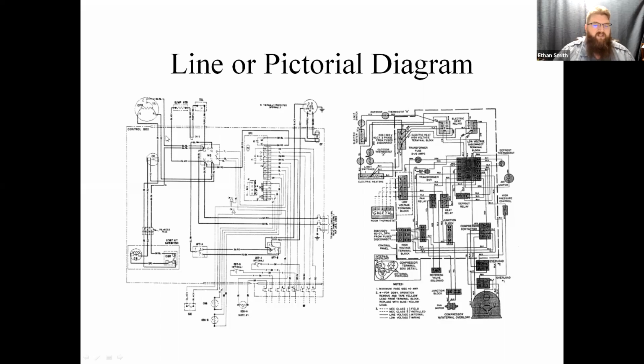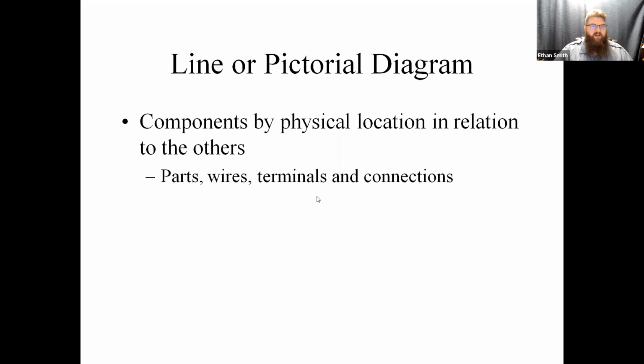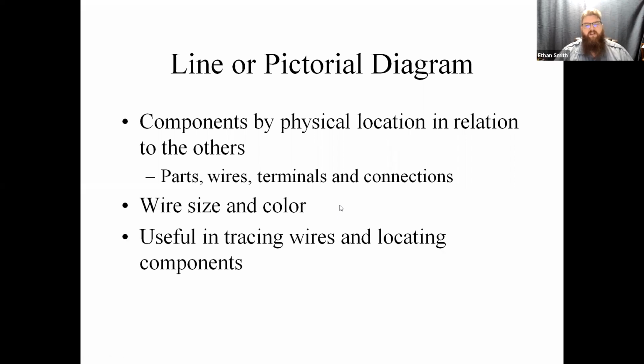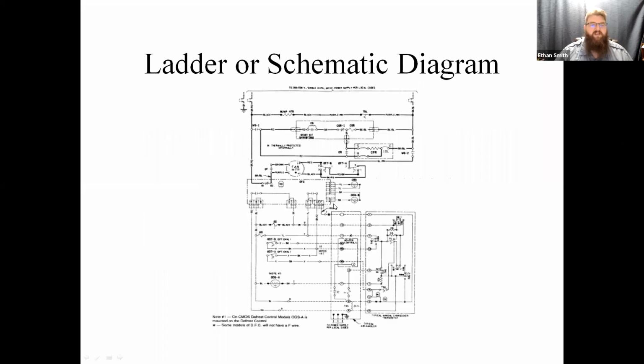It's very, very linear. I lived and died with a set of highlighters in my hand on these wiring diagrams, because I just couldn't keep track of the wires, so I physically traced the wiring diagram. It allows you to go from device to device very easily just by tracing your physical wires, and see all the switches it goes through out to where it controls whatever you're trying to control. So they can be useful for that. It usually shows physical locations, all the connection designators, wire designators, all that stuff is useful. This is really good for tracing components.